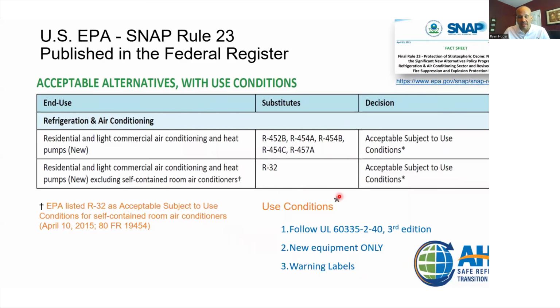The good news, I guess, if there is a silver lining, is that only 2 of these are going to be in play. 4 of these, the manufacturers have elected to not use. The bad news is there's 2 in play. So 410A is being replaced by 2 separate things depending on what manufacturer you're dealing with. For example, R-32 has been selected primarily by Daikin and any of the Daikin family of products, right? So Goodman, Amana, and those folks.